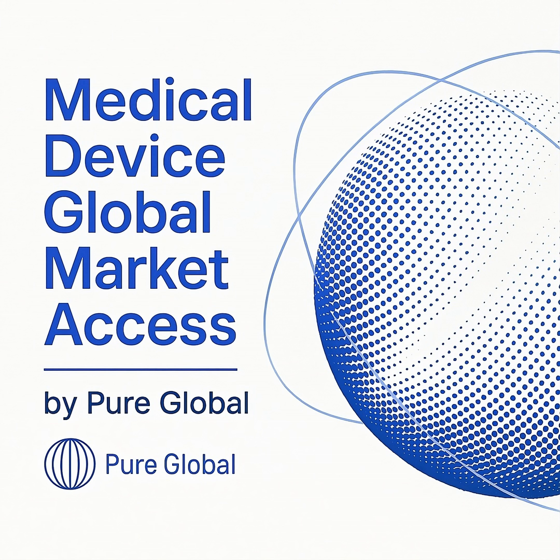The global nature of app stores also presents a challenge. A device might be approved in the European Union, but not in the United States. Manufacturers are now expected to use the geo-restriction tools provided by platform owners, like Apple and Google, to ensure their SaMD is only available for download in countries and regions where it has received the proper regulatory clearance. Failing to control the geographic availability of your device is a clear violation of the principle of controlled market placement.